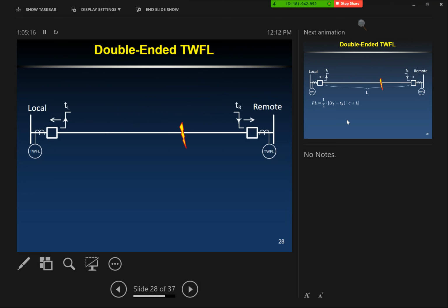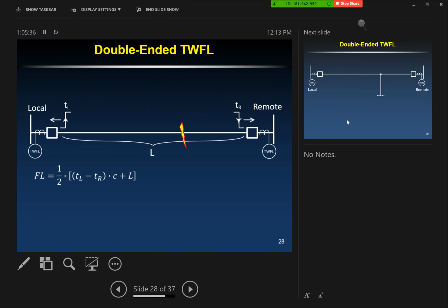event capture. So you have traveling wave relays installed at both ends. This is connected to a very high accuracy GPS clock. This is connected to a high accuracy GPS clock. They both record just that first impulse we saw on all those events. And that's all you need for the double-ended method. There's your line length. It's a very simple formula that gives you the fault location. Basically, you need your T sub L, your T sub R, the speed of light, plus the length of the line.